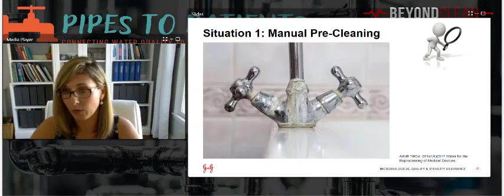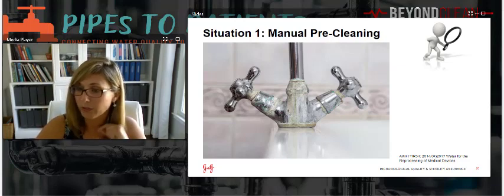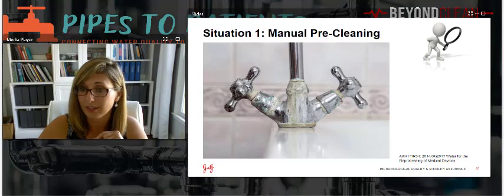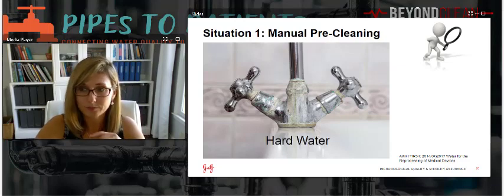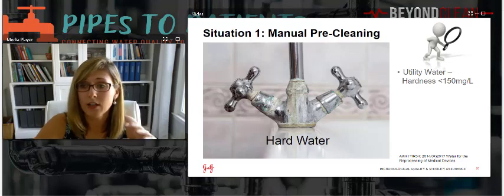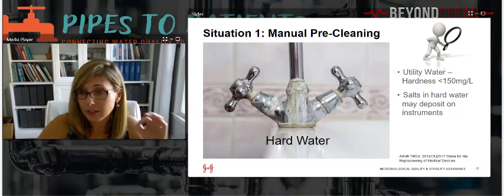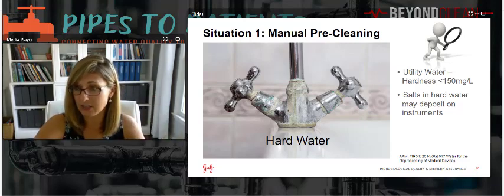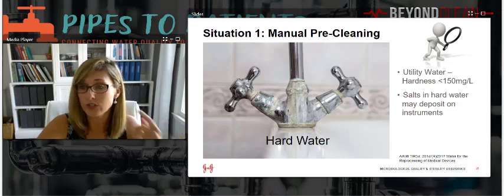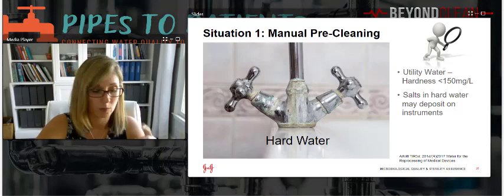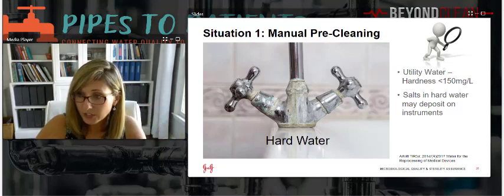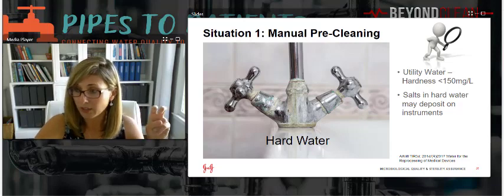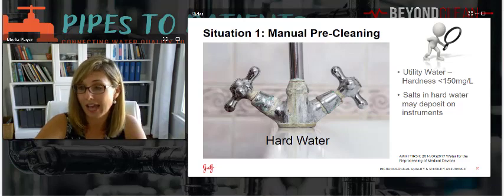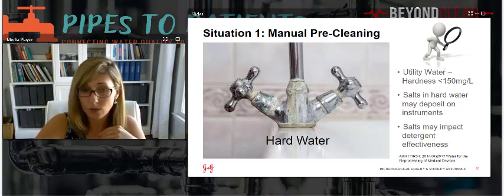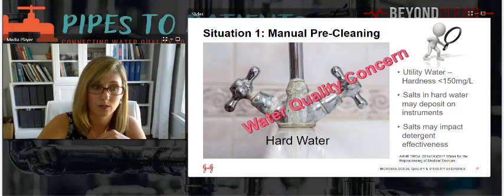So thinking about the manual or pre-cleaning step, if you see this on your faucets, do you think this is a problem? Yeah, it's an indication of hard water. So remember, the utility water has a hardness limit. Even that utility water that may be tap water, if it's not softened to an appropriate level, you could start seeing salts depositing on instruments as well as fixtures, as well as within your washer disinfector. So even that tap water should be of utility grade so that you're not having these types of problems, because those salts may impact your ability to clean and sterilize the devices. So it certainly is a water quality concern.